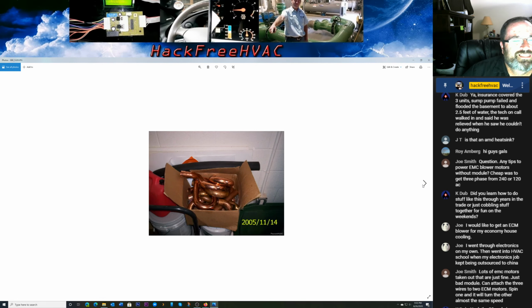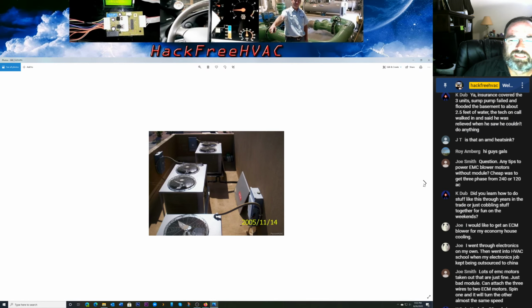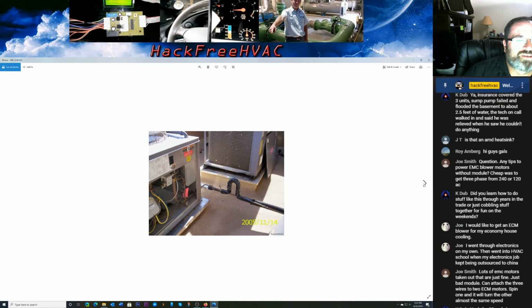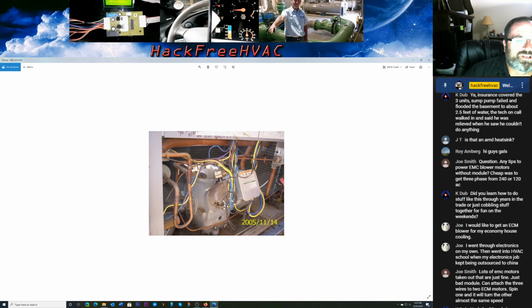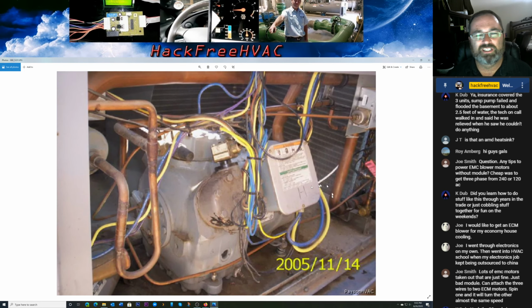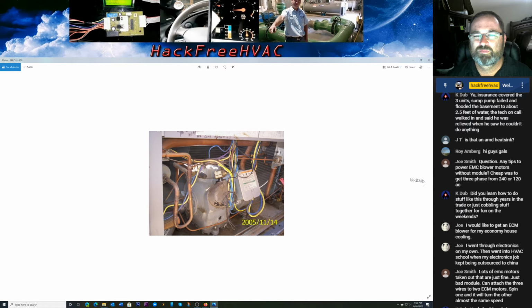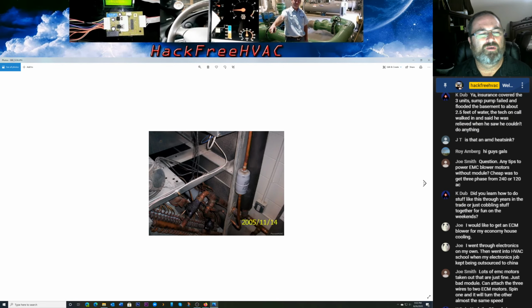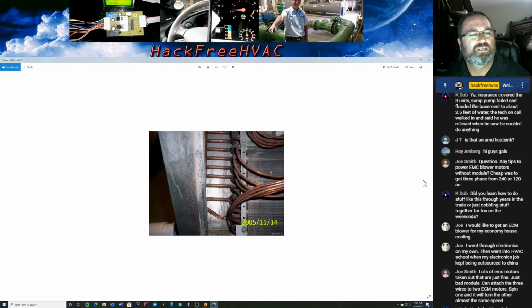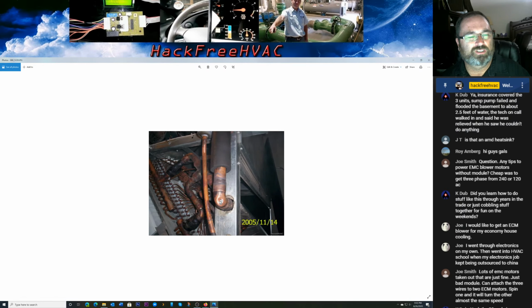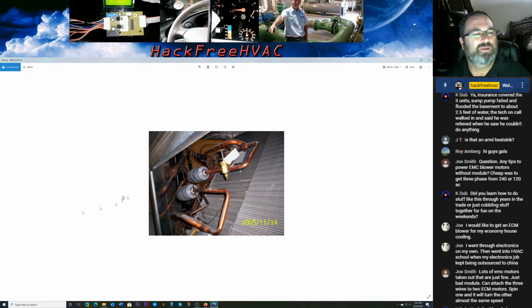Oh yeah, this company I was working for, I used to go behind their installs. I was still learning on this stuff. They were adding traps and everything, but look at the color on that head - they already torched it, man. Running these things out of oil, kept hitting the reset. So I found out what they did - they call it that they didn't put a solenoid to unload or to bypass one of the coils below when the compressor unloaded, so it wouldn't keep the velocity to keep the oil. I drilled a hole here like they said to, and I drained out a couple gallons of oil out of this sucker.